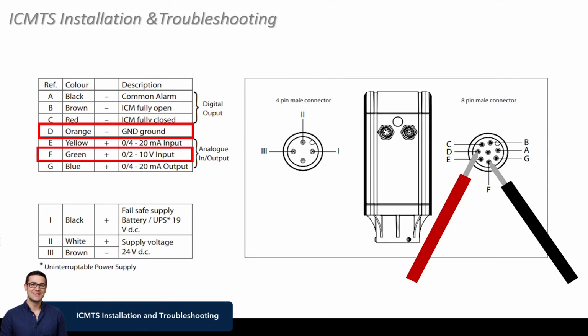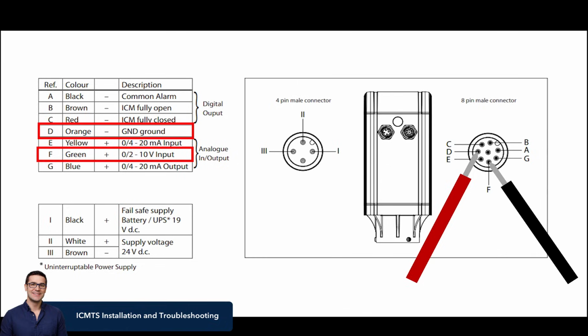If you're not sure if the valve's the issue or the controller is the issue, what you can do is take the 8-pin male connector off, and you can check from F and D. So F is your green, that's your 0 to 10 volt input, and D is your ground. This is coming from your main controller that is opening and closing the valve. If you're not getting a signal from there, maybe it's something from the controller side. If you are getting a signal and the valve is not moving, well, maybe now you need to manually open, manually close, check if there's dirt inside there. So this is one extra check before you deem the valve a failed valve.